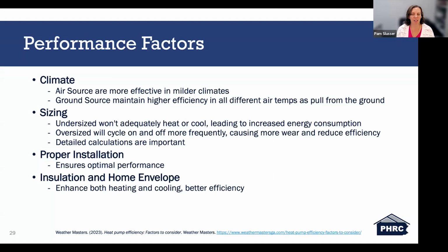So getting those detailed calculations is very, very important with getting the proper sizing, looking at the home's square footage, the layout, heat loss characteristics, all of those different areas. And then when you're talking about proper installation, installing the system and the ductwork is extremely important as well. Proper installation by a certified HVAC professional is important. That helps to ensure optimal performance and the longevity of the heat pump.